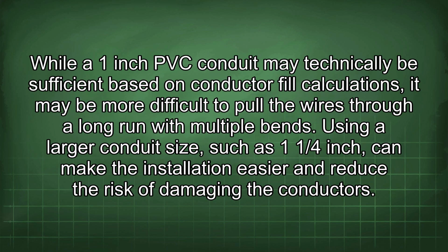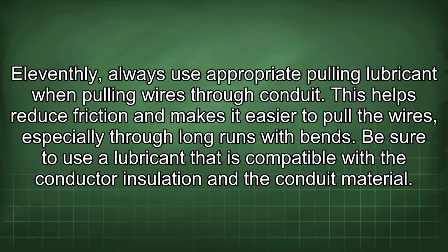While a 1-inch PVC conduit may technically be sufficient based on conductor fill calculations, it may be more difficult to pull the wires through a long run with multiple bends. Using a larger conduit size, such as 1 1/4 inch, can make the installation easier and reduce the risk of damaging the conductors. 11thly, always use appropriate pulling lubricant when pulling wires through conduit.